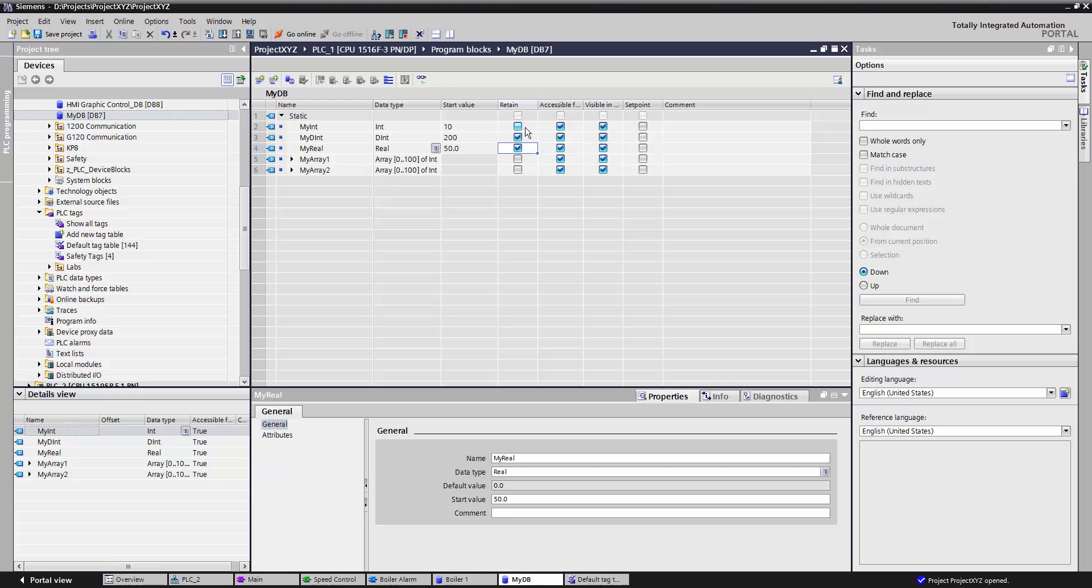If I do not have retain selected, then every time the PLC is powered on, the data point will default back to my start value. If I do have retain selected, then the data will simply become what it was when the PLC was powered off.